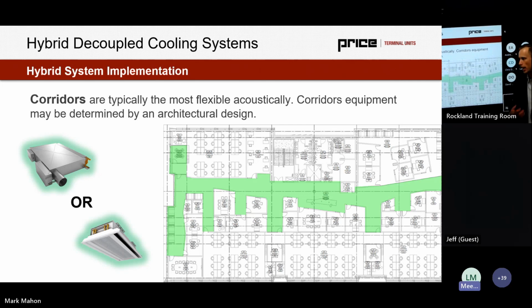Sure. So the rationale was it's a very transient space. It's not frequently occupied. The actual mixing of air is less critical, and the chilled beam could work better because of that. I think there's some great rationale there. Any thought process for why we'd maybe go the other direction? So you could potentially argue we could treat it as a bit of a VE opportunity, cheaper. Jason in the chat, thank you. We're on the same wavelength there.